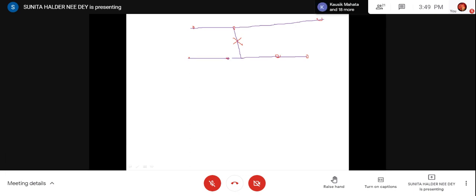So this will be the connection as I have shown. But we always prefer ring main, because if there is a ring main, then your voltage distribution is better. So as in the example I have drawn here, this will be the current. From there you can calculate current on all these branches using KVL and KCL. Then where will be the minimum potential point? Say if you get this one as the minimum potential point, but in this particular case I have drawn, this should not be the minimum potential point, but this will be the minimum potential point, because further to that there is one radial line also.